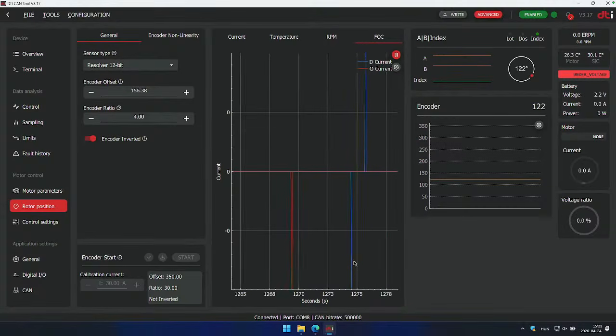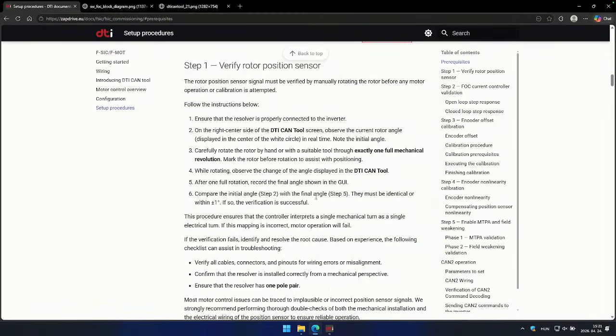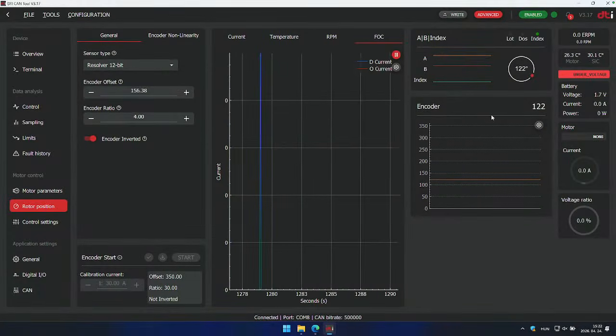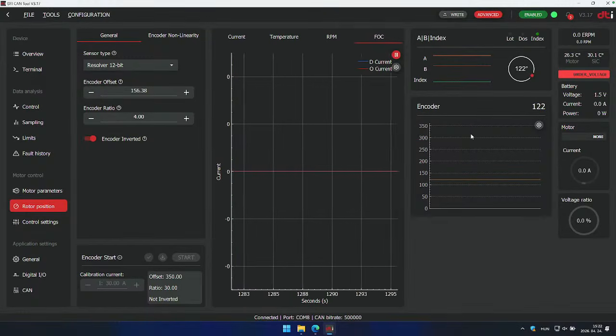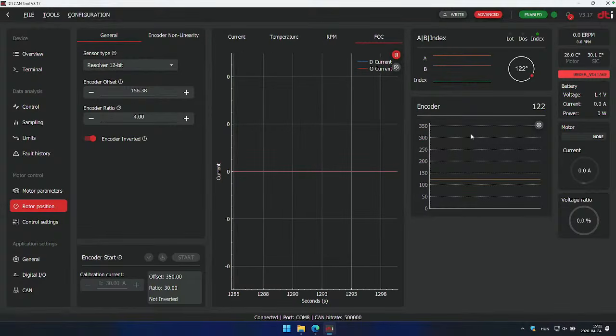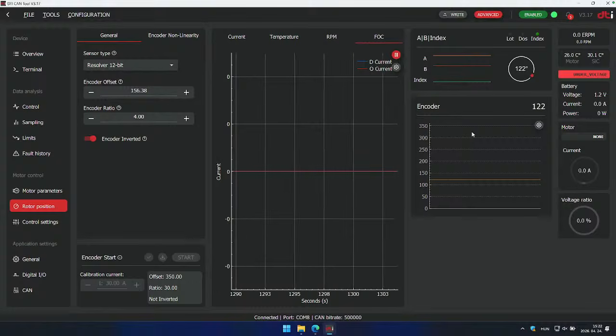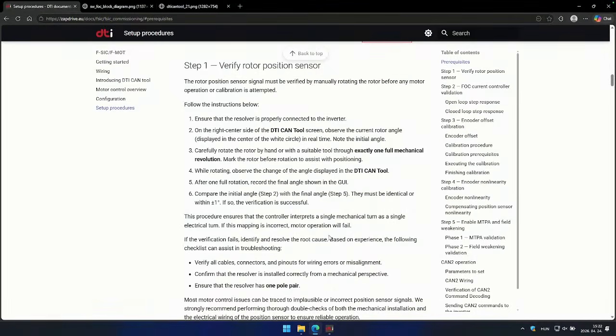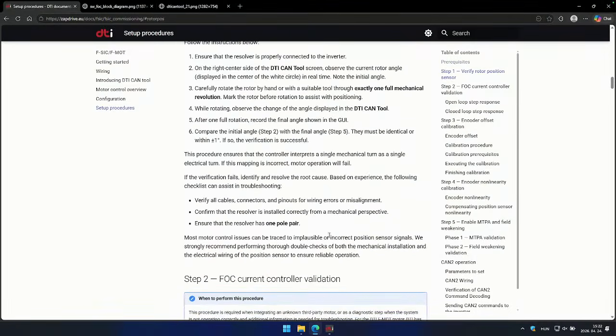The theory here is that you mark the rotor shaft, move the rotor shaft exactly 1 rotation, and observe if you get exactly 1 rotation in the real-time graph, because it means that 1 mechanical rotation means 1 rotation in the inverter and firmware, so it's synchronized, and that's what we would like to see. If we do not see that here, then we have to verify the cables and resolve the issue.